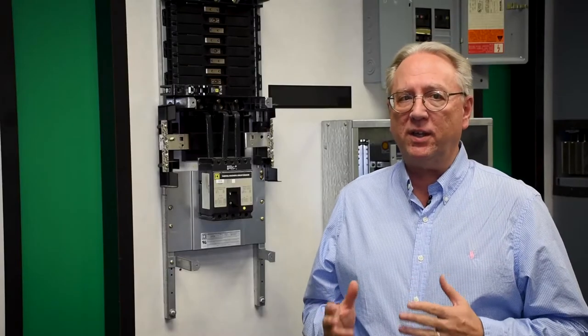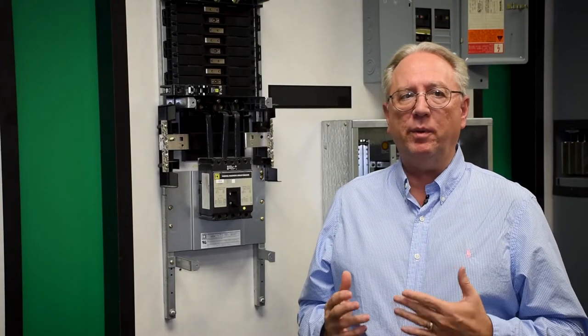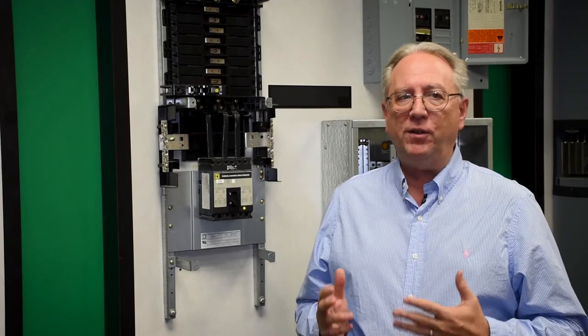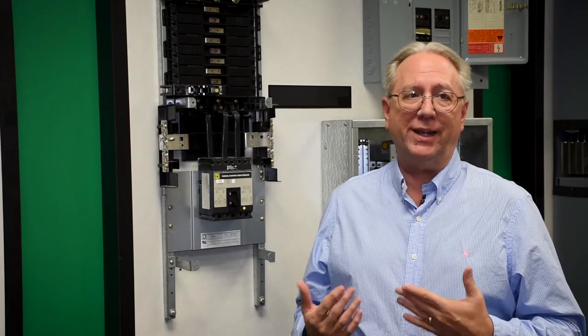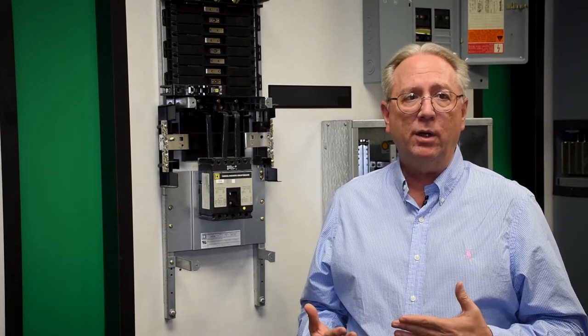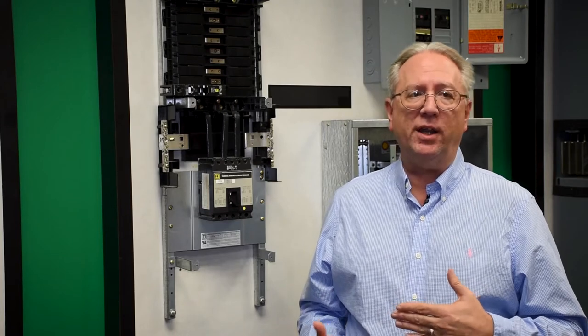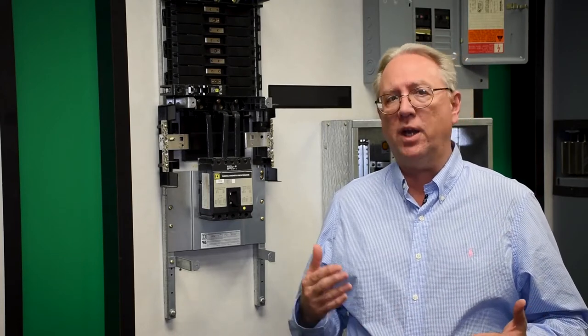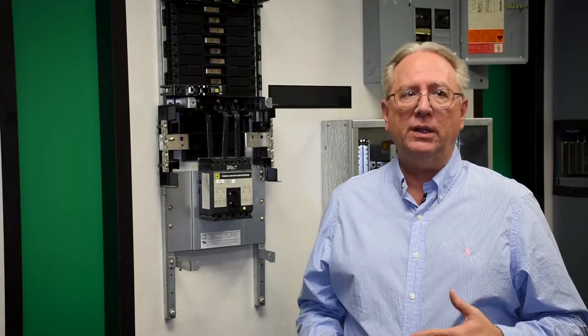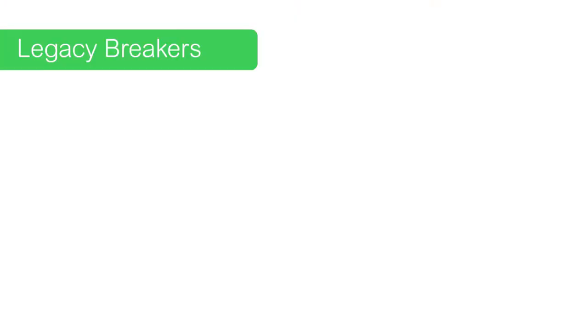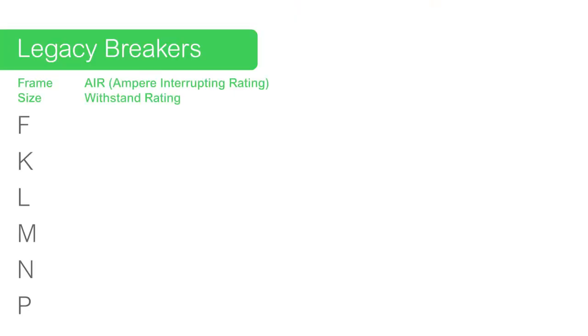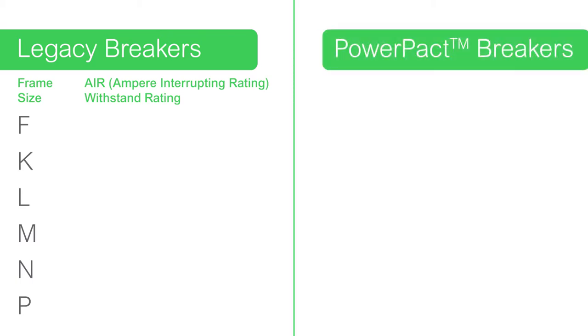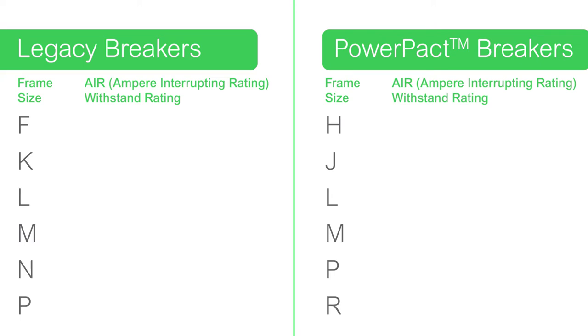So what happens if a contractor calls and needs to replace a breaker? If you have the first two characters of the catalog number, you can quickly identify whether you're talking about a legacy breaker or a PowerPact breaker. The legacy breakers are F, K, L, M, N, P. The PowerPact breakers are H, J, L, M, P, R.